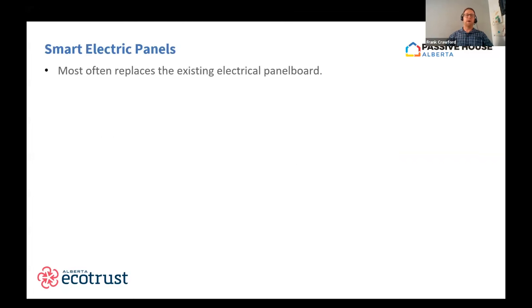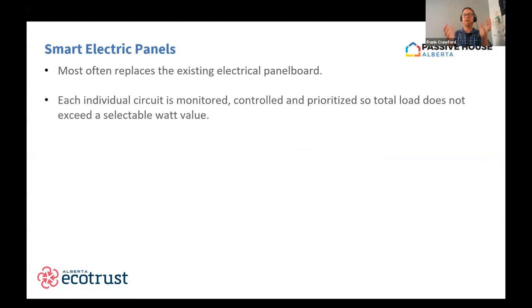Another type of equipment, one step up from a load share device, is called a smart electric panel. These most often replace the whole electrical panel. So they're best for new builds, or if you have lots of different circuits that need to be monitored. The advantage of these is each individual circuit on the panel is monitored, can be controlled, and can be prioritized so that the total load never goes over that selectable value. So you could connect a whole bunch of things on there. Say, I never want to go over 100 amps, and it says, here are my priorities. As I start to get close to that, these are the circuits you turn off.